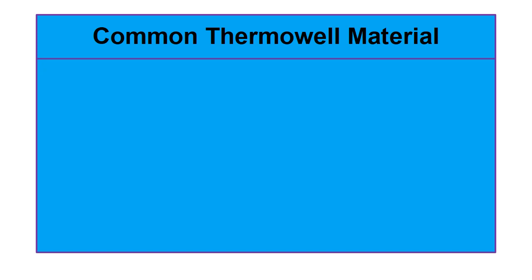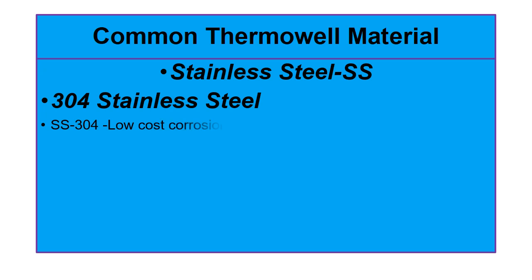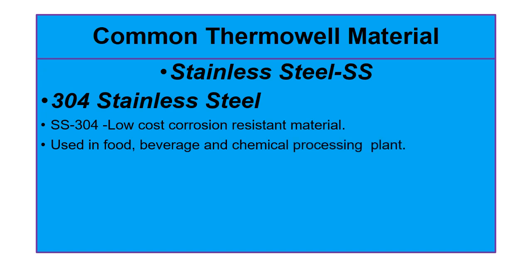The next material is stainless steel or SS. Stainless steel is the most popular material, and different material grades are available. Grade SS 304 is a low cost corrosion resistant material. SS 304 is extensively used in food, beverage, and chemical processing plants where good corrosion resistance is required. SS 304 is also available in a low carbon version, generally known as SS 304L.